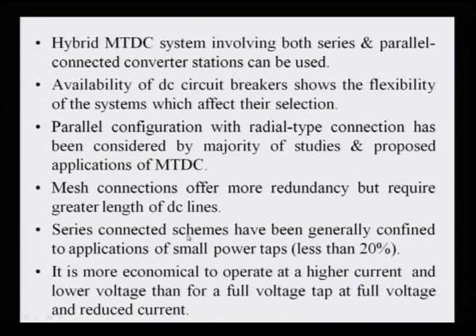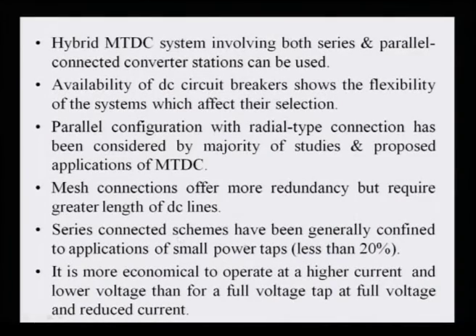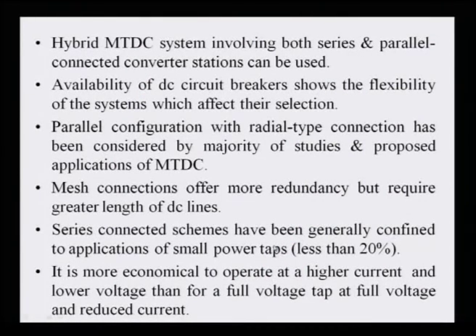Series-connected schemes are generally confined to small power applications. In the series connection, current is constant and voltage changes to control power. If you increase current, losses increase and voltage drop becomes significant. The current can be minimized but the limited voltage constrains the power, which is why series schemes normally operate at lower power ratings. It is more economical to operate at higher current with lower voltage since insulation requirements and converter station costs can be reduced.